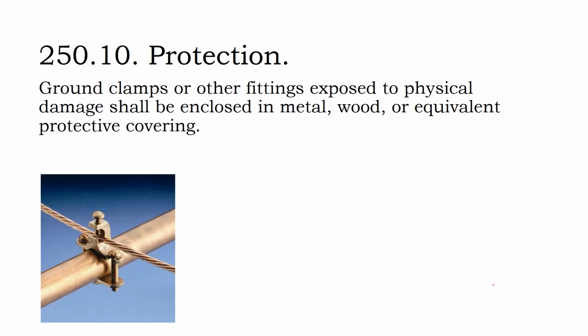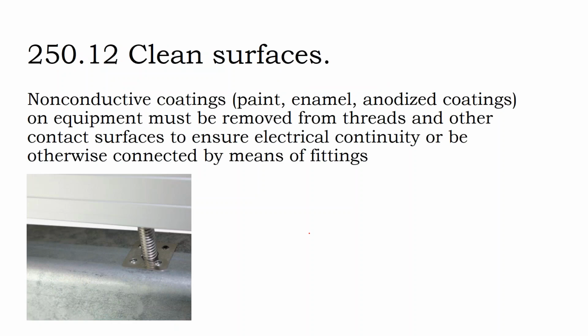So generally, you're going to connect to your ground rod, your copper wire. They call this an acorn, and it's just a lug, but that has to have a protective barrier around it. You might just cover it with PVC and put it into the ground. We have to remember that our metal parts are given an anodized coating so that they can be protected from the elements. But that anodized coating also increases the resistance of metal, so just doing a metal-to-metal connection is no longer grounded.